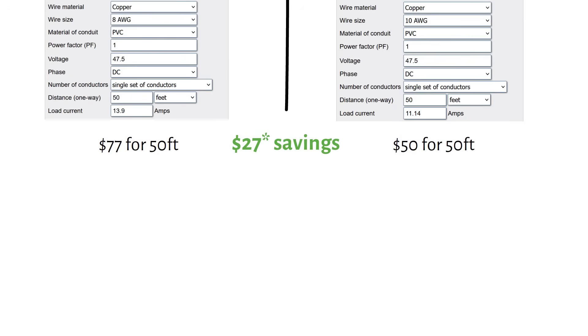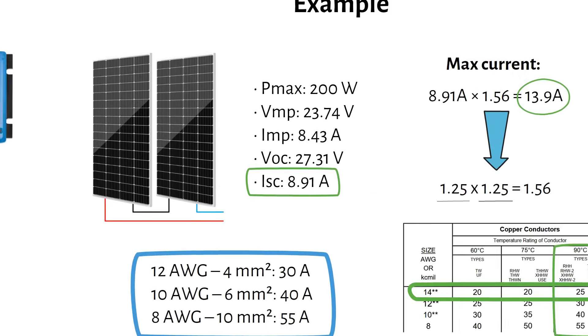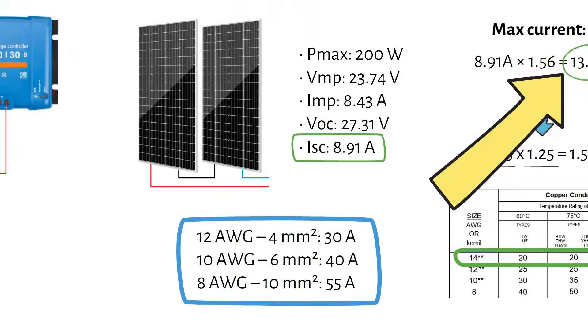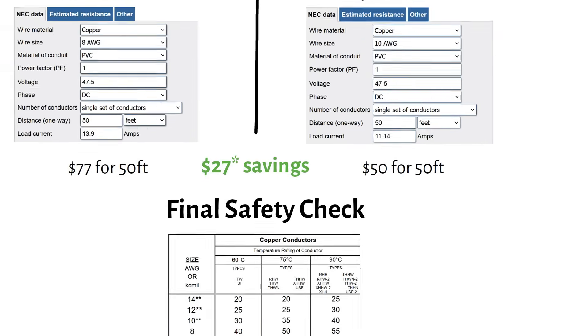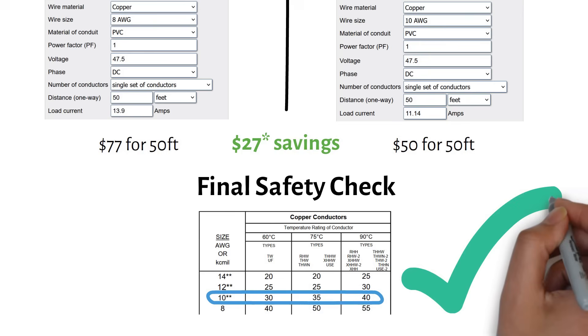Before we're done, we have to do one last check. We need to make sure the calculated cable of 10 gauge or 6 mm square can carry the maximum current in the wire. Remember the previously calculated maximum current of 13.9 amps? Let's see if this cable can handle the current. From the table, 10 gauge can carry 40 amps. So we're good here.